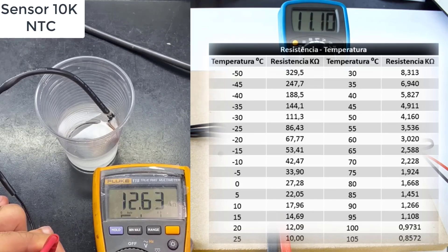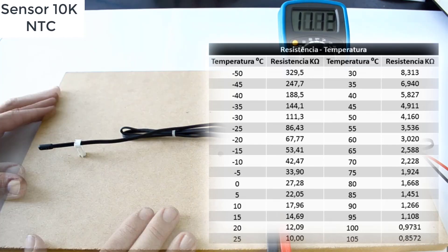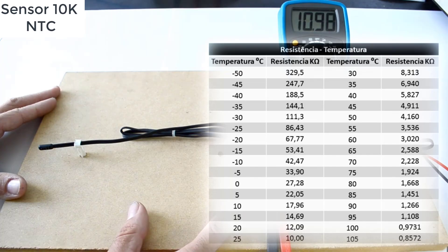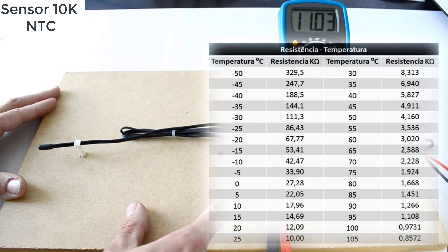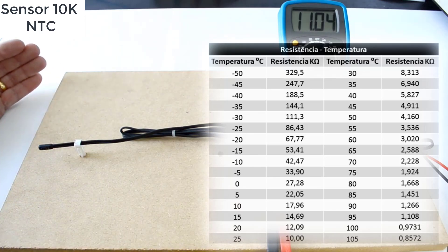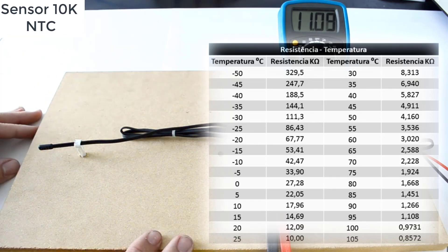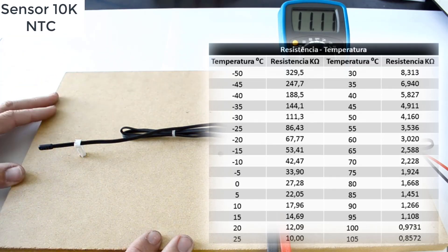In the table, you can see that if the temperature is at 20 degrees it should give 12.09K, and if it is at 15 degrees it should give 14.69K. The values are around these with a variation of 1%. If you are measuring on your equipment and testing a sensor, you should compare the theoretical value with the ambient temperature. If the value is too far off, it indicates that the component is defective.